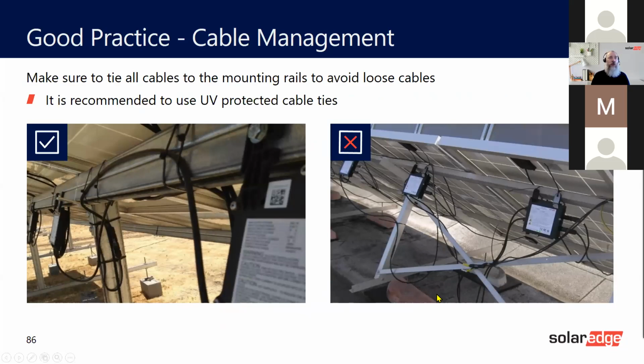What you don't want is this cable rubbing - see these cables underneath here - maybe rubbing against the connectors, or rubbing against the ballast here, the brick or the roof itself, or a tile. And also don't secure the optimizers like this - these are very old optimizers with cable ties.